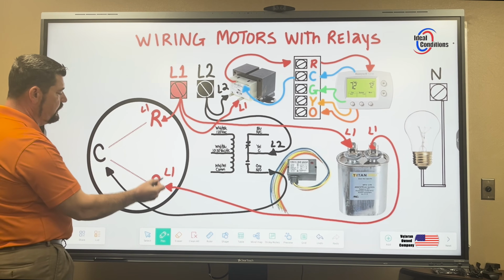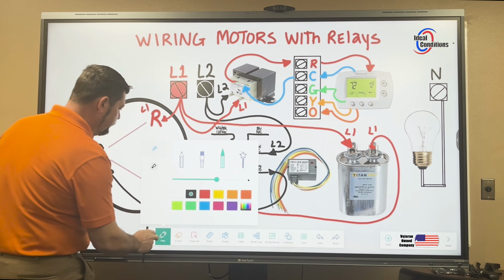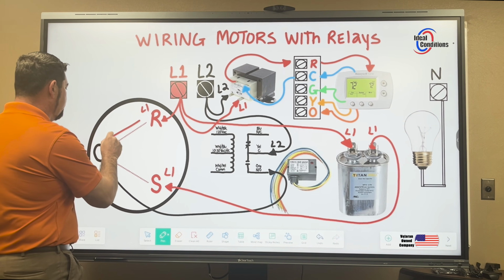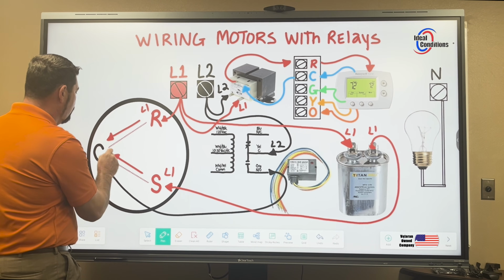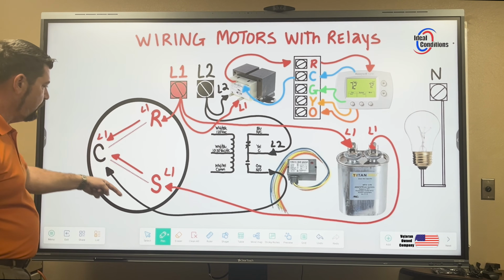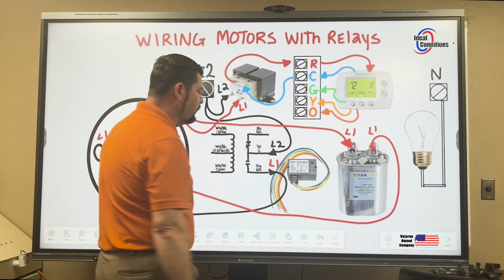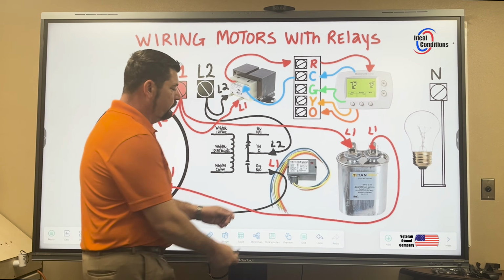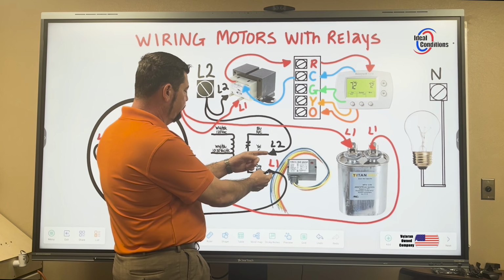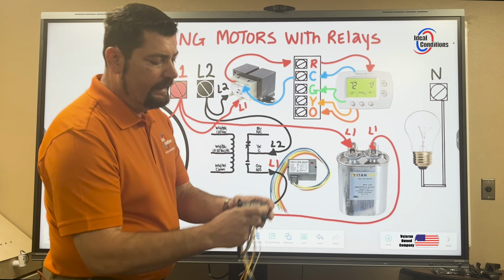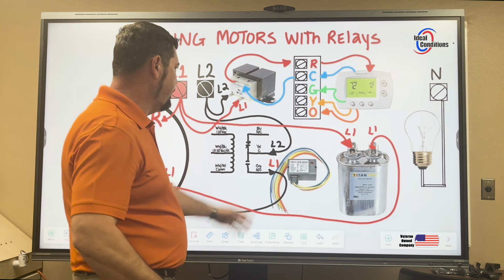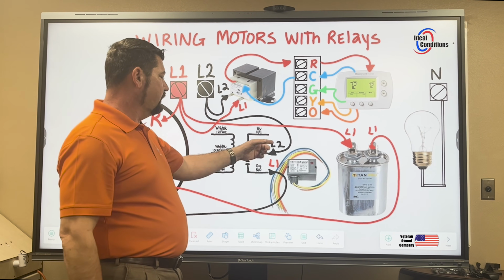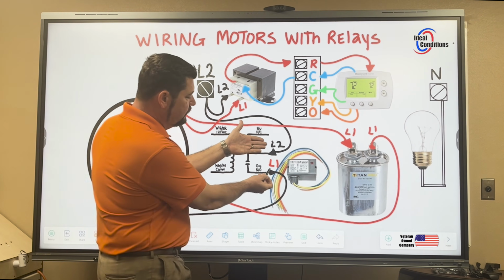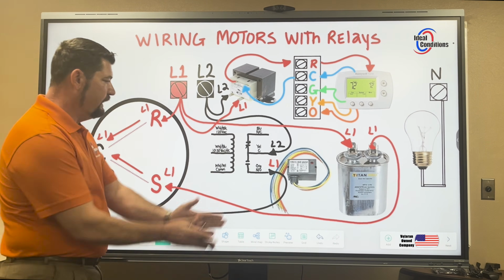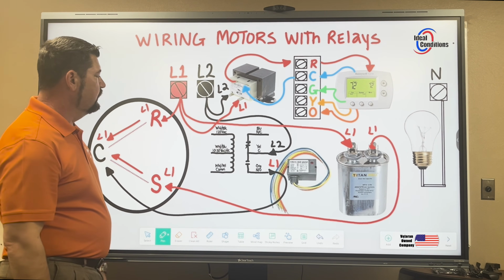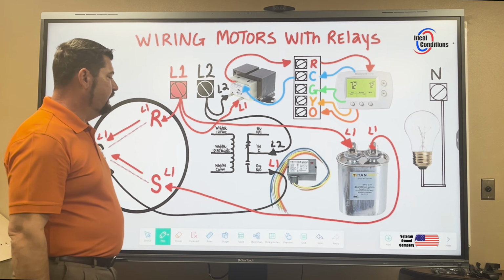We're saying that if I have L1 here and L1 here, and I follow the path of electricity, then that path of electricity puts L1 right here. And if you follow the path all the way back to here, that means L1 is also present right here. So if I wanted to check my relay, say I was getting a red light here on the relay telling me, hey, you have coil voltage, say I had 24 volts here, and I still had L1 here and L2 here, and the motor wasn't running, I would actually read that difference of 240 volts, two different legs in different directions. I would read that on my meter. That's how I would know that I have a bad relay.